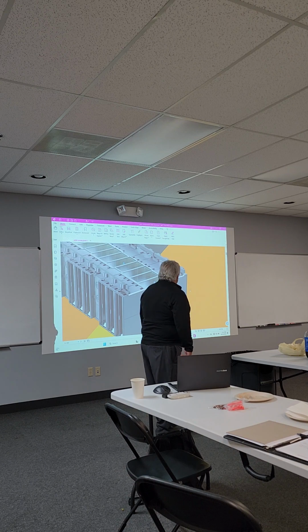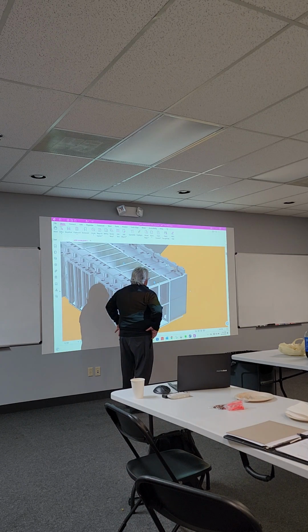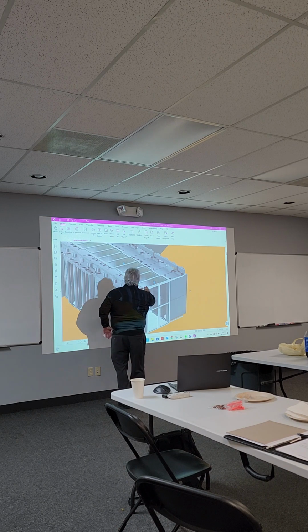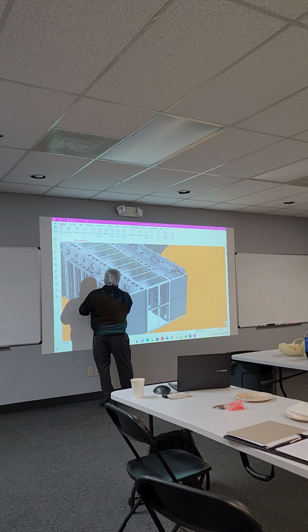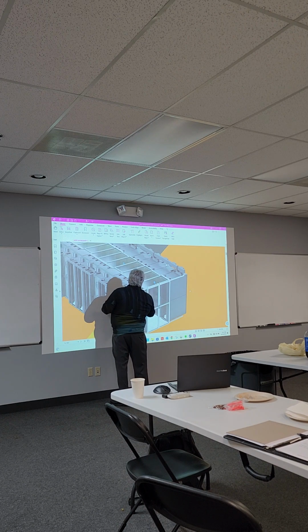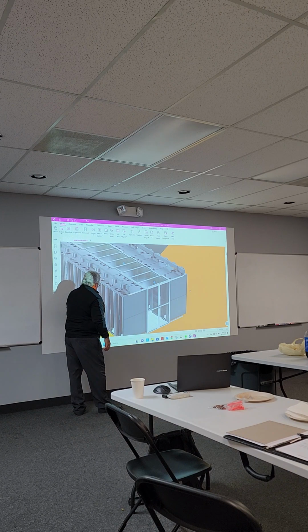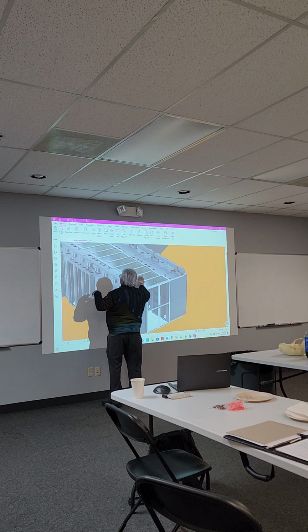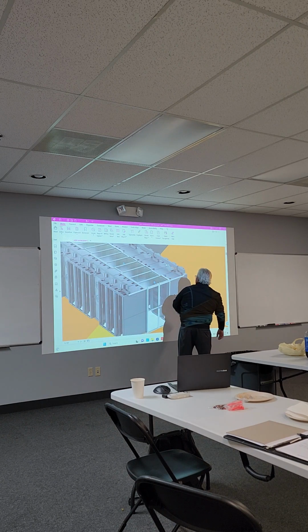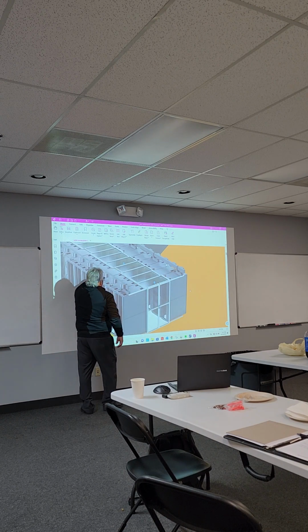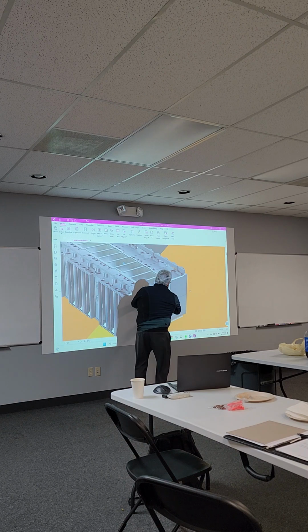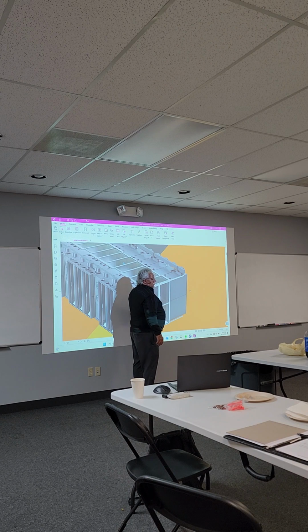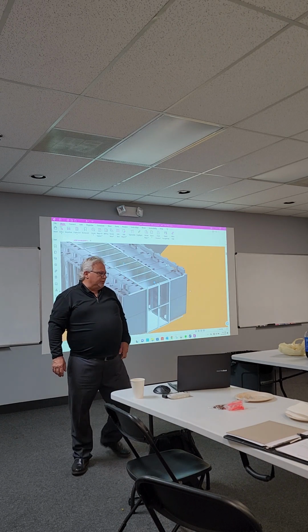So that's why using containment is really -- I can't stress it enough, it's just huge. The reason for putting a roof on here is that you avoid overlapping. If this is the cold aisle and this is the hot aisle, if this wasn't contained, and you have perforated tiles blowing air up, or units in the row, that air will come over the cabinets and shut units off. That's why we like to put a roof on it. But if we're doing one thing, I'd either put a door or a curtain here to stop that air from coming. So there's all kinds of different things you can use.